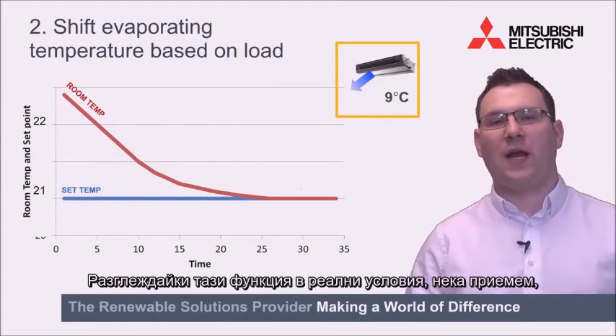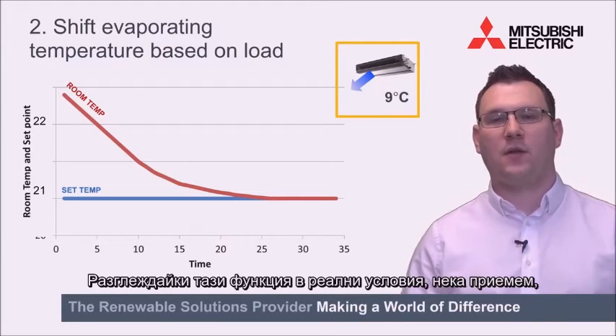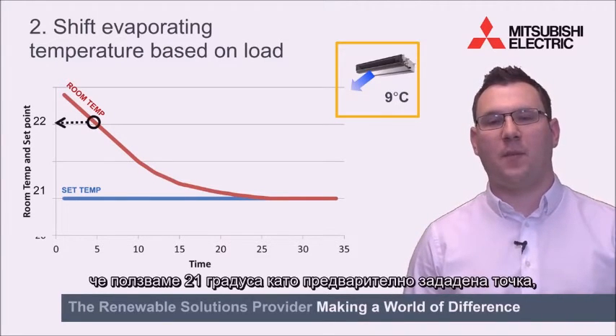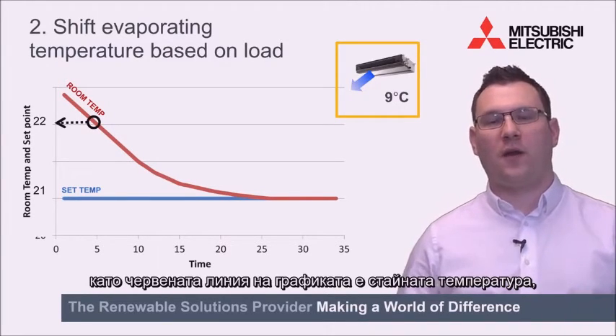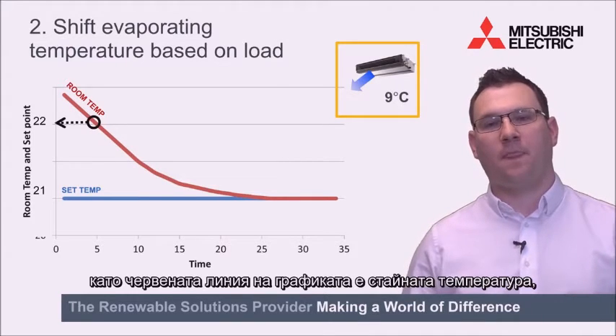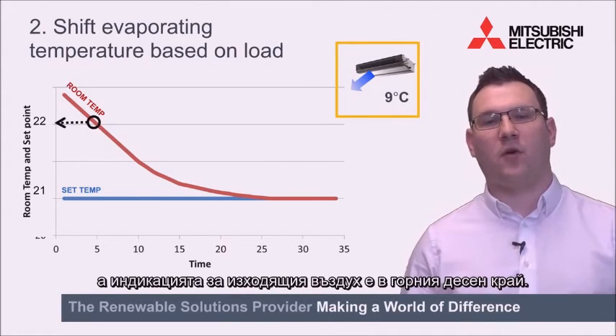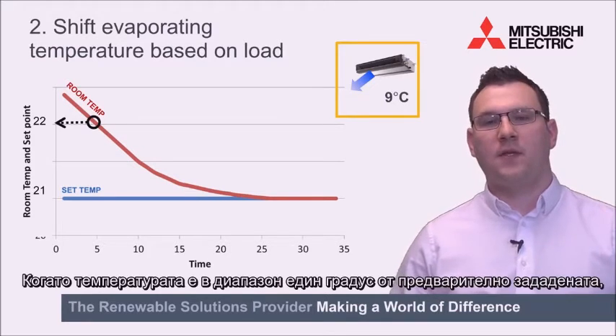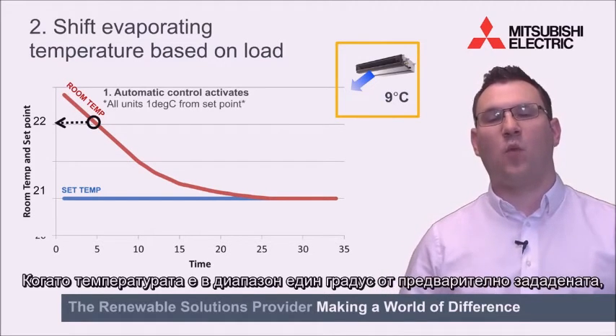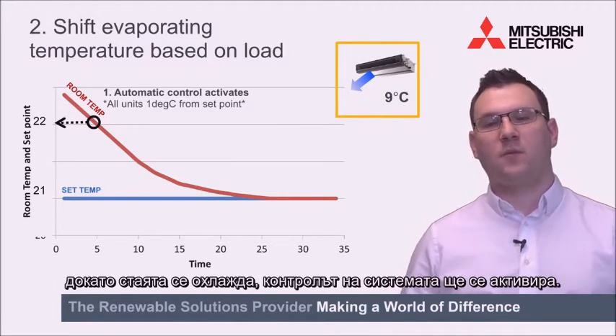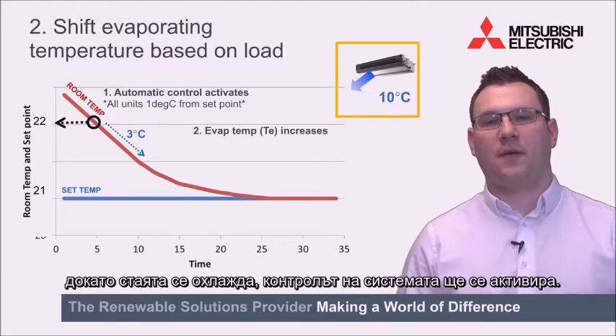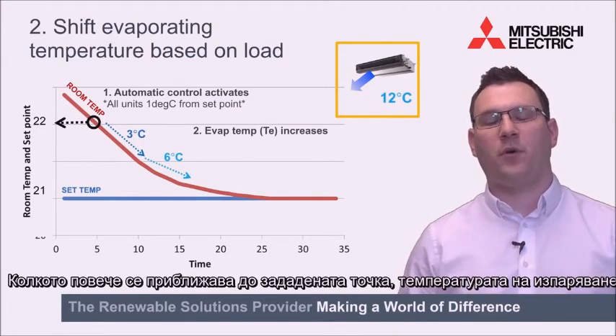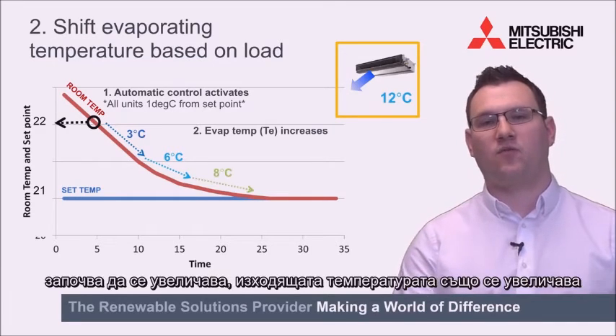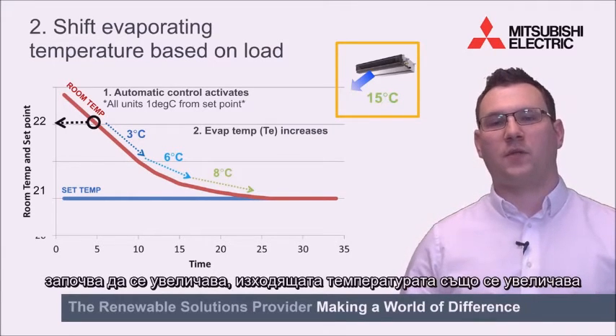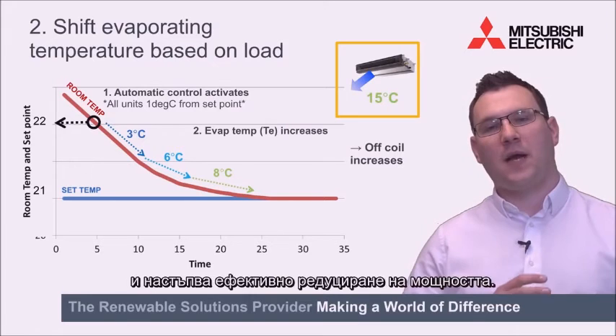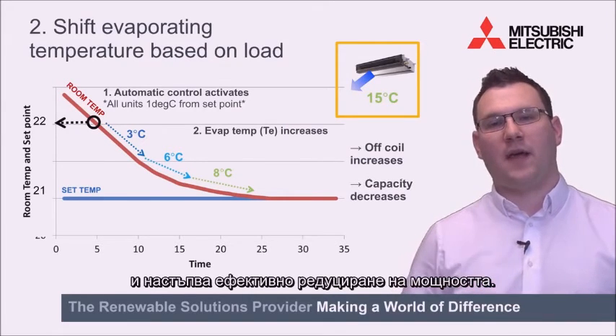Considering this function in a real application, let's look at if we're using 21 degrees C as a set point, with our red line on the graph being the room temperature, an indication of the air off in the top right hand corner. So as the room is being cooled and it gets within 1 degree from set point, the system control will activate. As it gets closer towards set point, the evaporating temperature starts raising, the air off temperature starts increasing, and the capacity reduction is actually in effect.